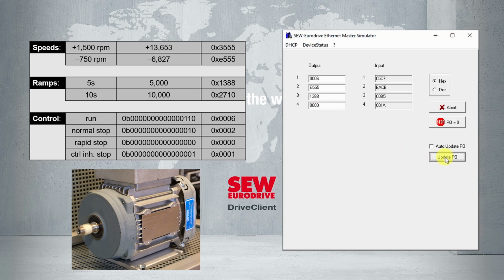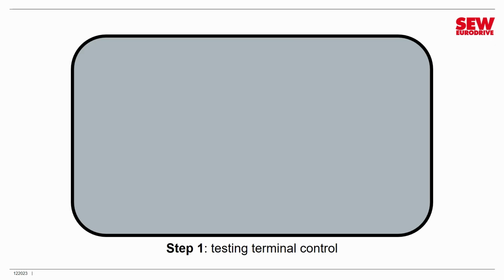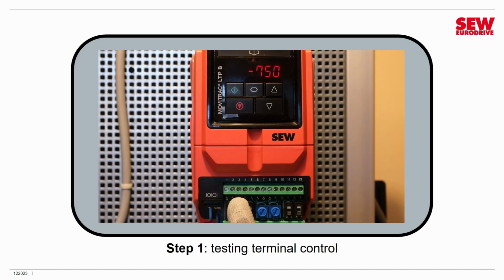So that will get us rolling. And now we're going to switch over to the terminal control, and we're going to start seeing what we can do with it. First thing we're going to do is try the forward reverse switch. So I'm going to turn DI2 on, and that's going to reverse direction. You can see it overrides the field bus direction.